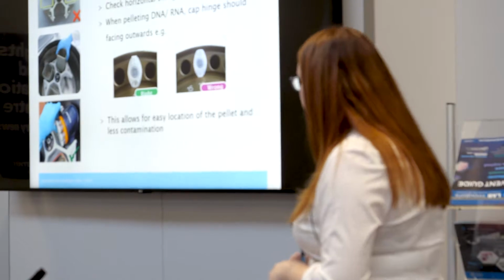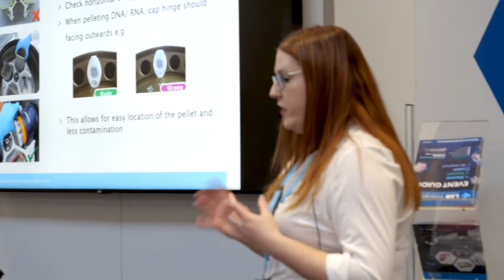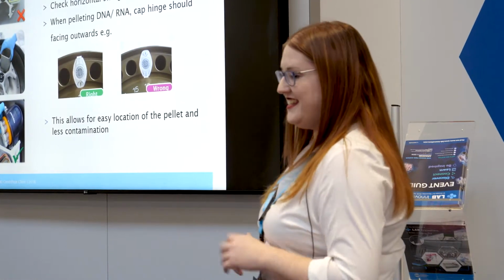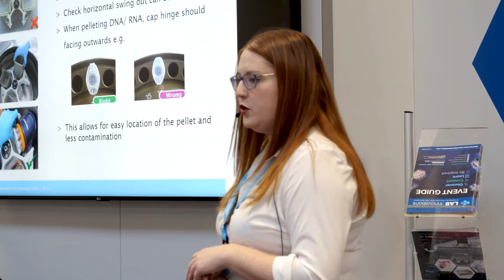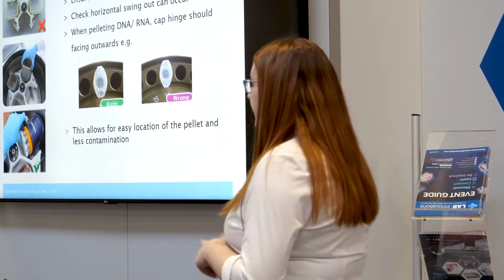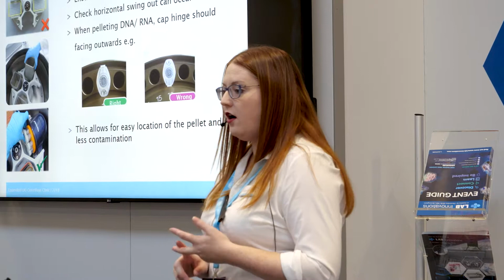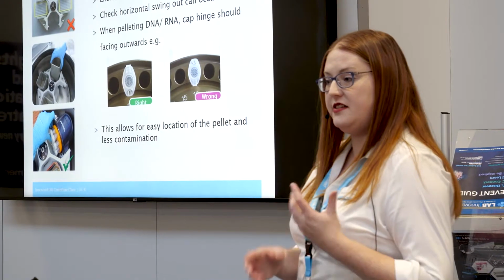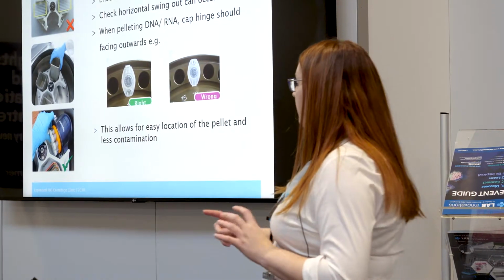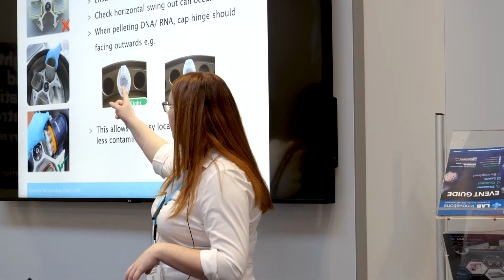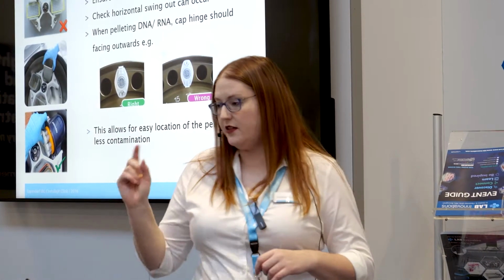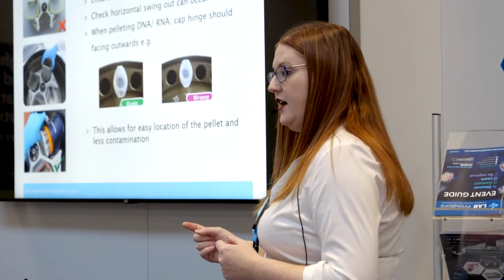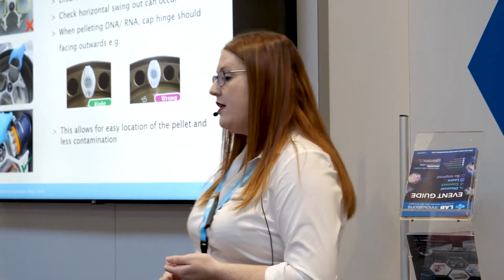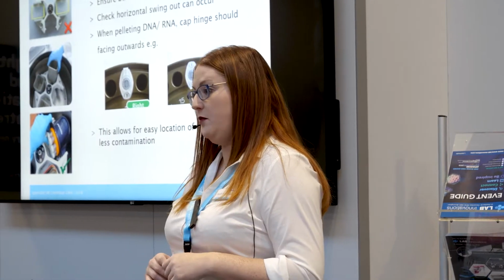When it comes to things like the smaller tubes, we recommend consistency, at least, in how you put your tubes in the rotor, particularly if you're working with something like DNA or RNA where you might not be able to visually see the pellet, because then you know that if you spun it like this, you know where the pellet's going to be. It's going to be on that side of the tube at the bottom under the hinge, which means you can pipette out any supernatant without disturbing your pellet.